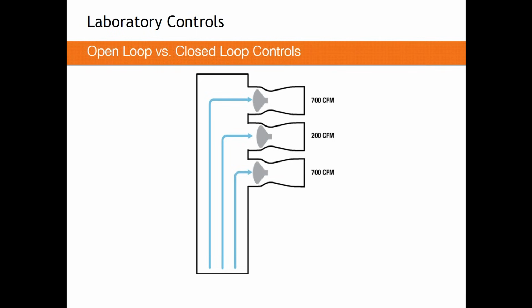The spring and cone assembly will automatically, mechanically, naturally take up that change in pressure, and they'll do it instantaneously. No controller had to be involved whatsoever because pressure and airflow are mechanically not linked together. So that's the fundamental difference between open loop and closed loop controls. It is really this application right here.